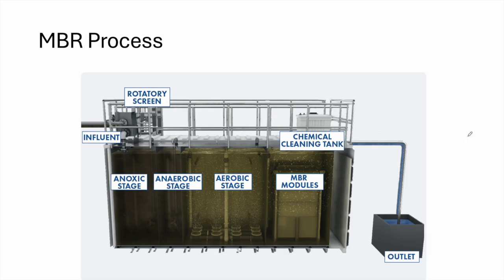For the MBR, we have a totally different technology. What we see here is a packaged MBR system — an MBR system housed in a container that can be moved, pre-assembled, and easily placed anywhere. For the MBR process, the influent first undergoes a screening process as primary treatment. This screening is very crucial; we usually use a fine screen to highly reduce total suspended solids.